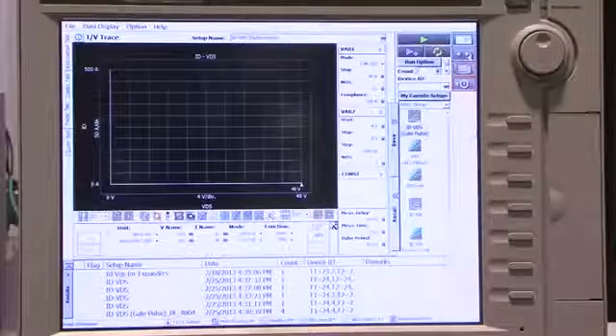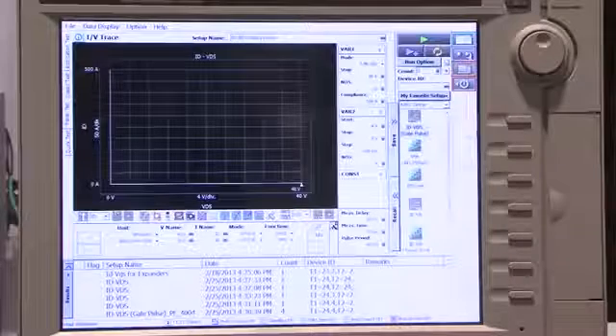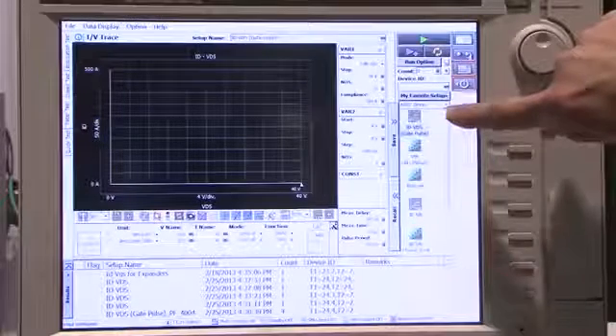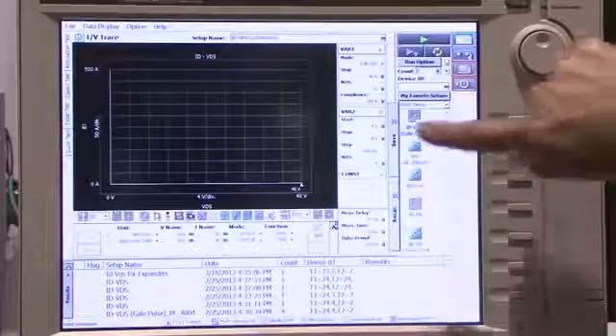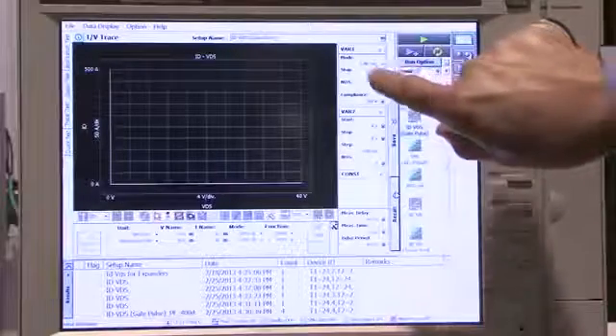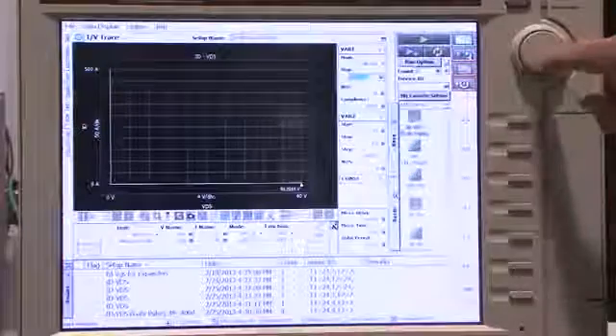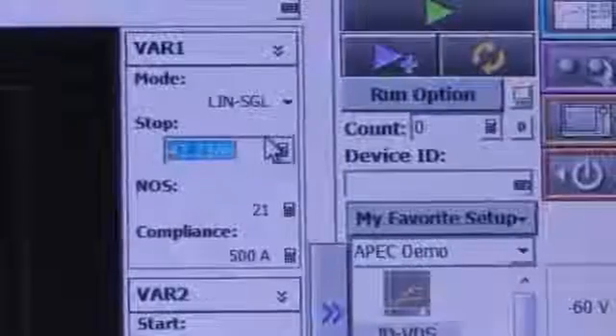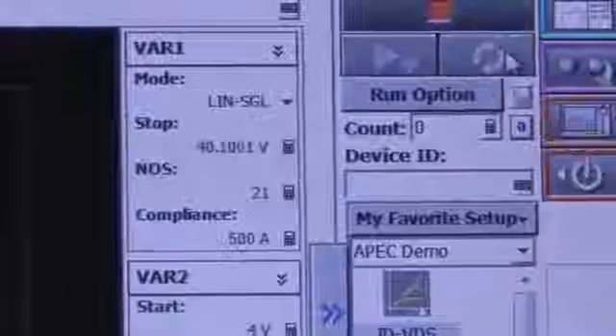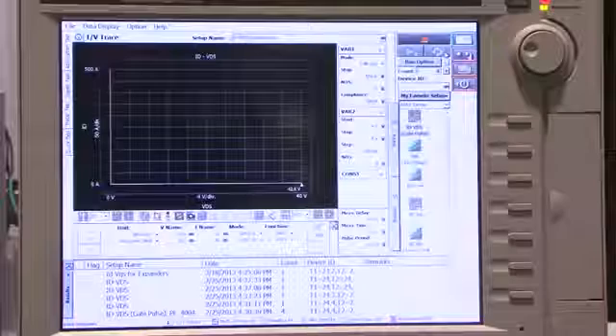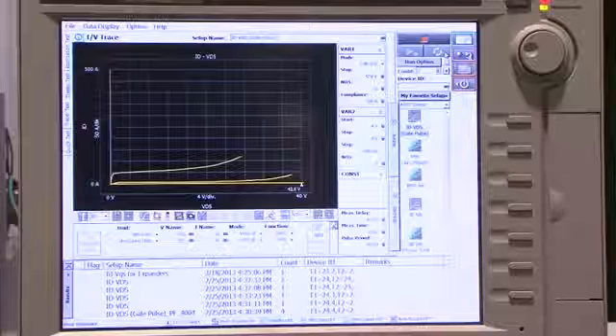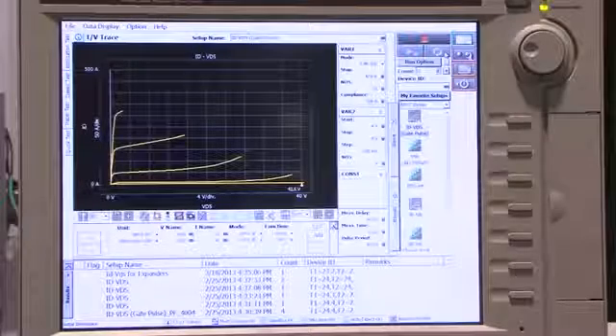Okay, so I'm going to start off by showing you the IDVD measurement of the MOSFET at 500 amps. So here I've got my saved test and all I have to do is select it and do a recall. And in this case, I'm actually going to go ahead and dial down a little bit. So I want to start a little bit lower just to show you how this works. Now I'm going to go ahead and start the repeat function here. And you can see that I'm starting to generate my family of curves. There you go, my IDVD curves.